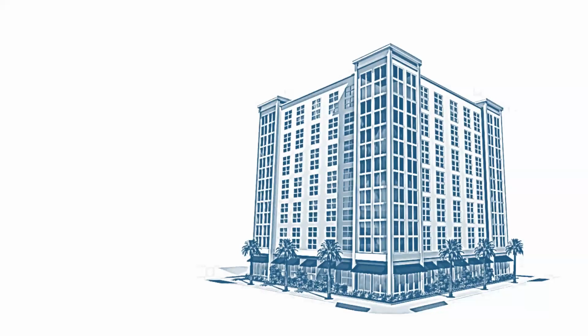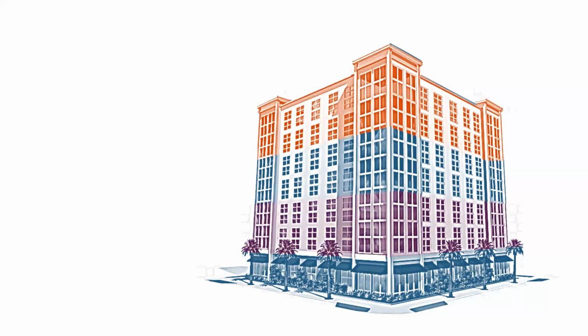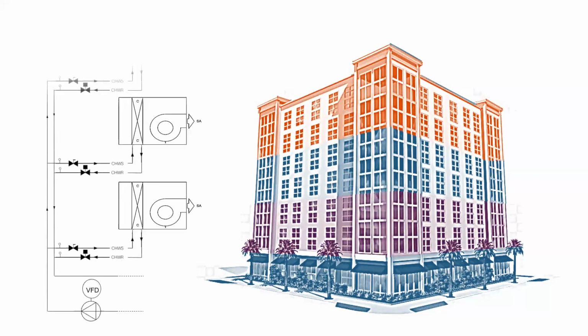So moving on, a pressure-dependent system creates a situation where each zone is hydronically dependent on all the other zones. Again, pressure-dependent systems, meaning that a change in zone B may affect the flow rate and heat exchange in zone A and zone C. In this example, we have this building.